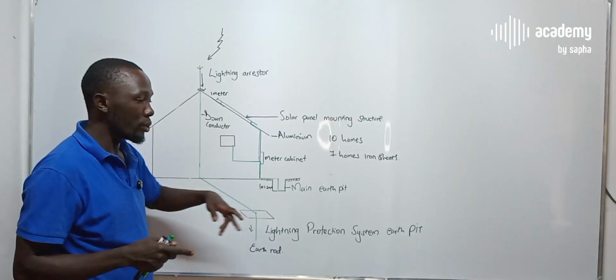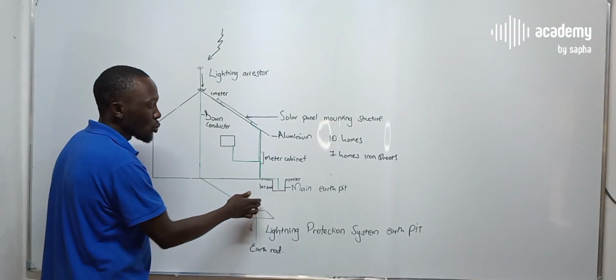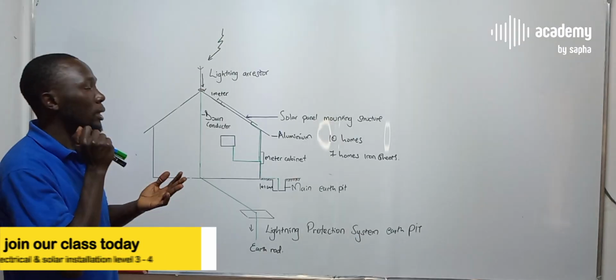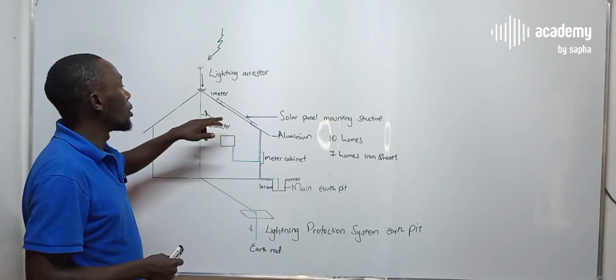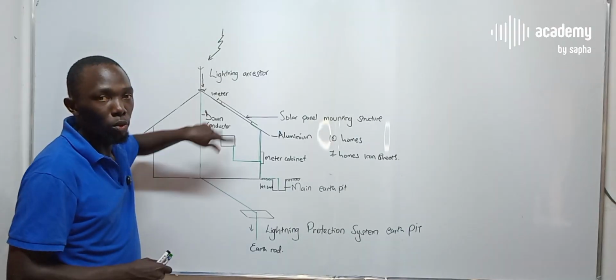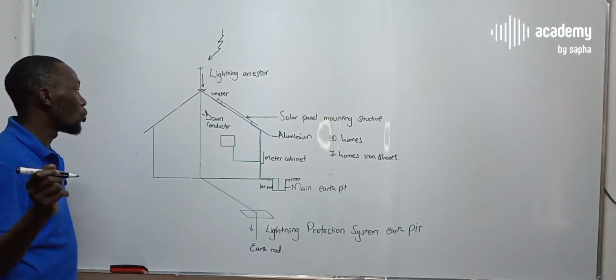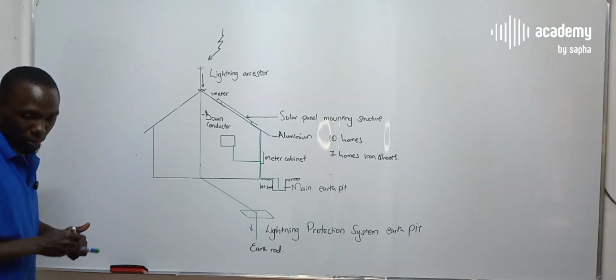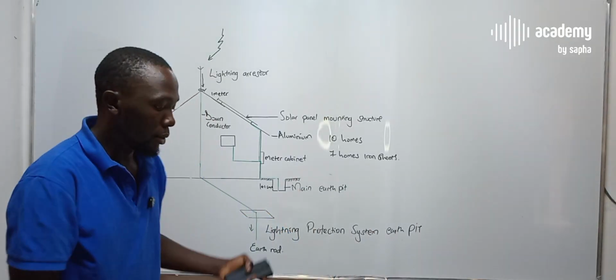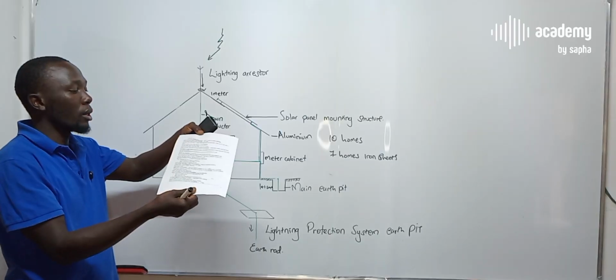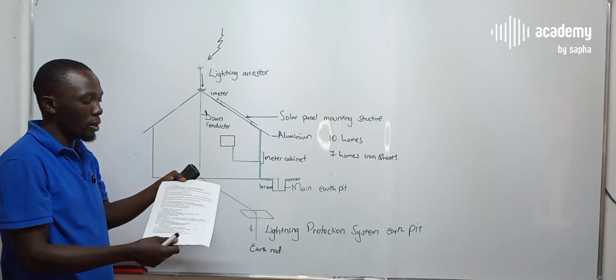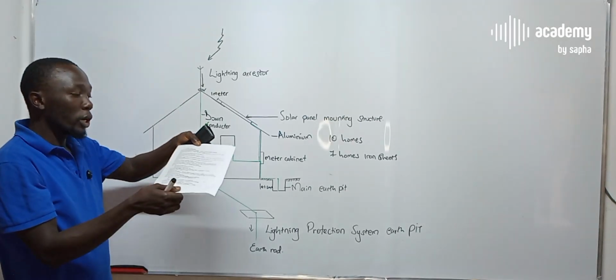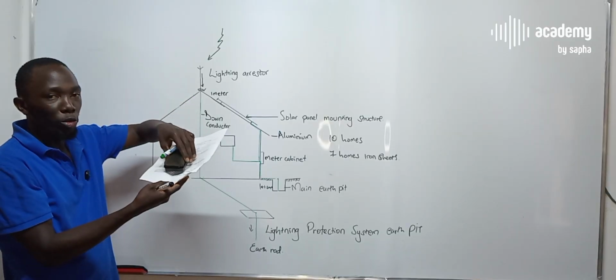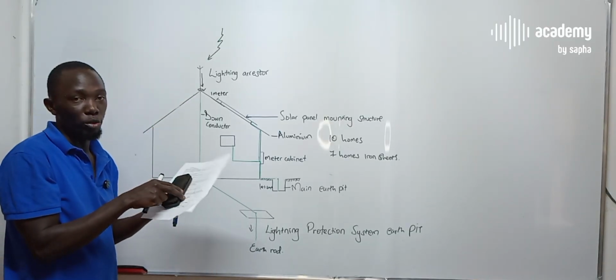The distance between this earth pit and this one, and number 2, the zone. If this one is 1.5 meters away from the wall, this one can go a bit further, probably 2 or 3 meters away from the wall. Another thing, you are advised that the solar panel mounting structure should also, something to keep in mind. For example, this is your roof structure, and you have got a lightning arrestor up there. So when this happens, the solar panel mounting structure should not go directly on top of your iron sheets. That is one thing also you have to keep in mind.